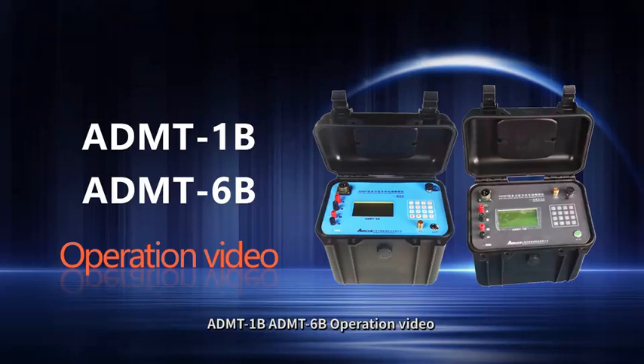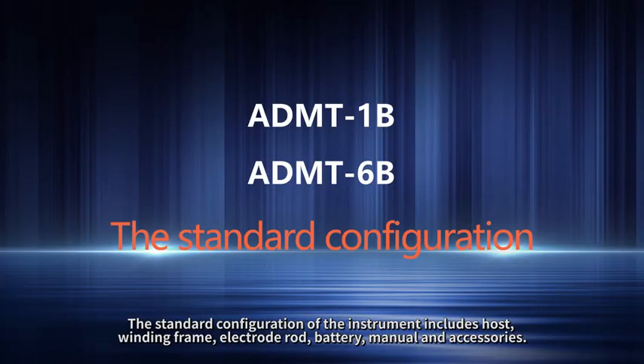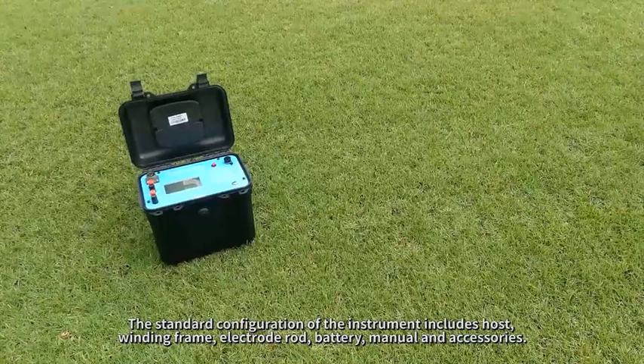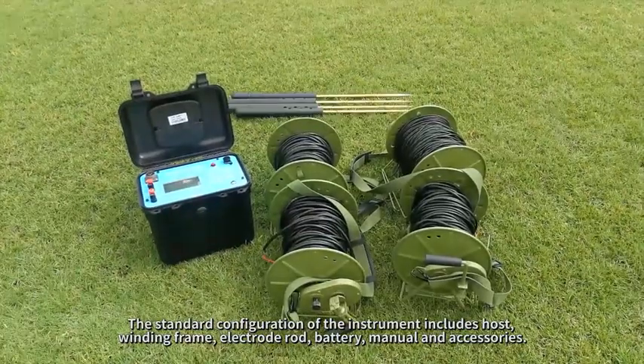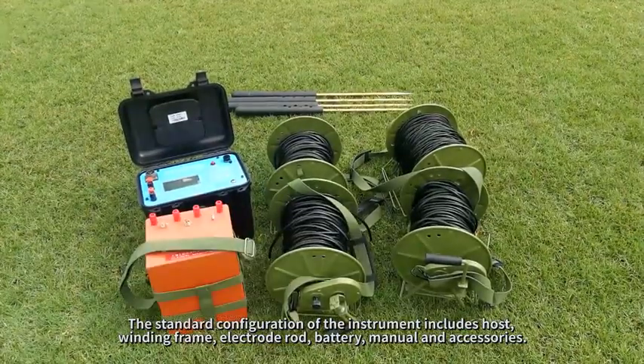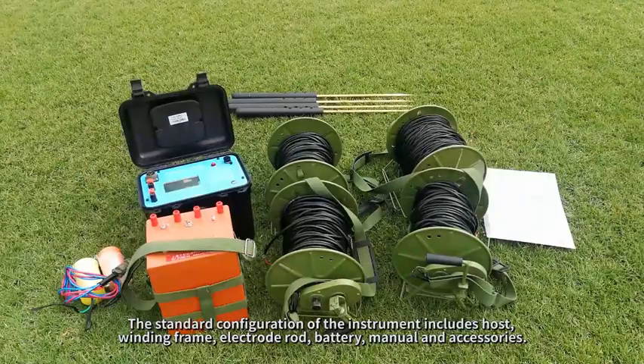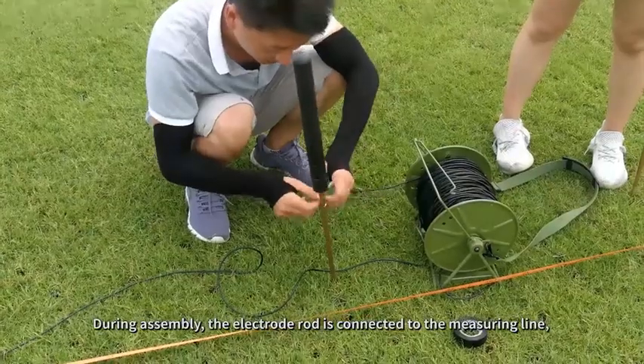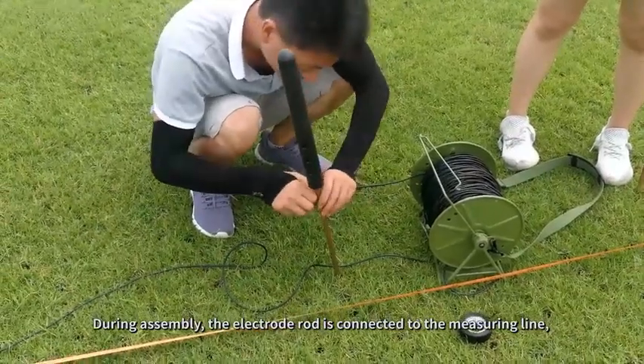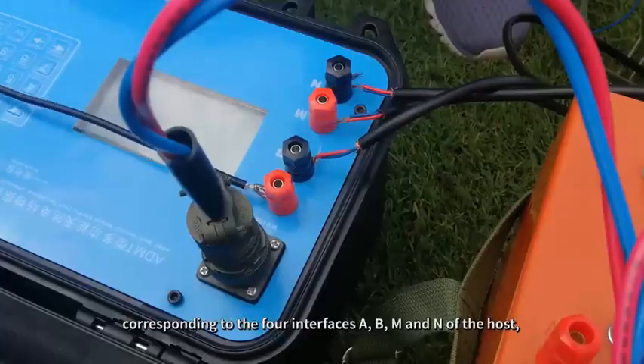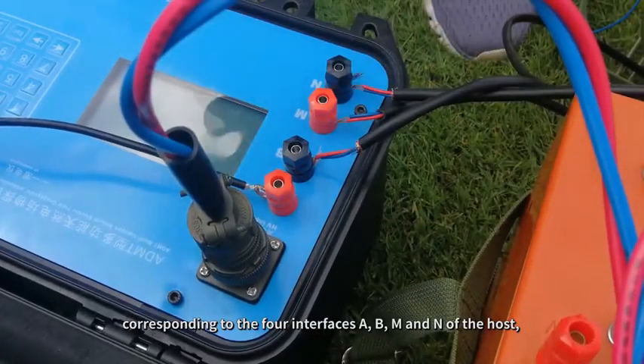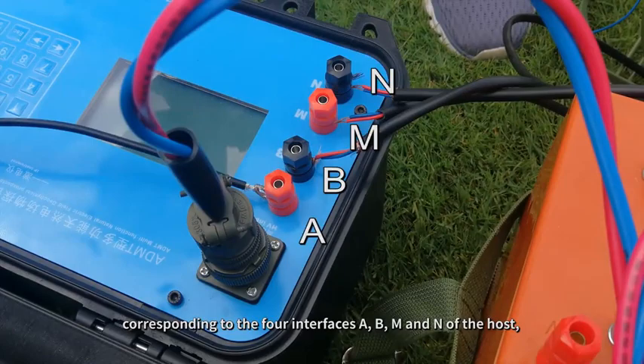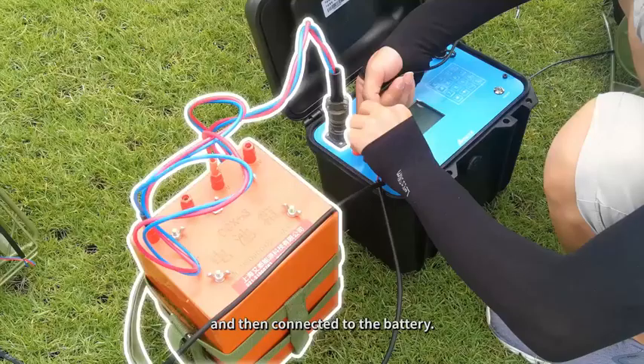ADMT-1B, ADMT-6B, Operation Video. The standard configuration of the instrument includes host, winding frame, electrode rod, battery, manual and accessories. During assembly, the electrode rod is connected to the measuring line, corresponding to the four interfaces A, B, M and N of the host, and then connected to the battery.